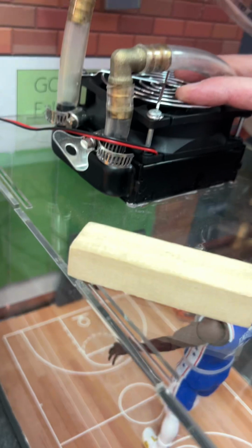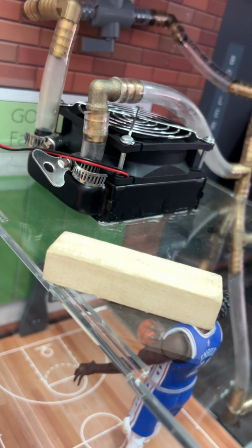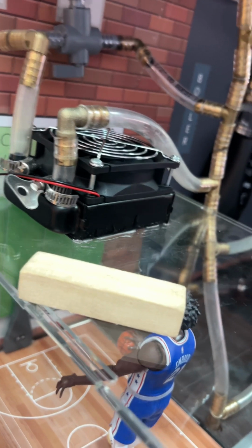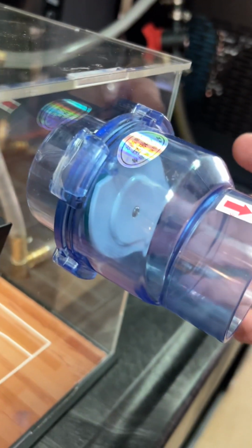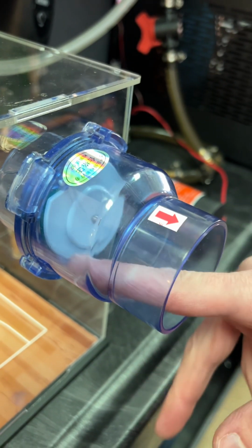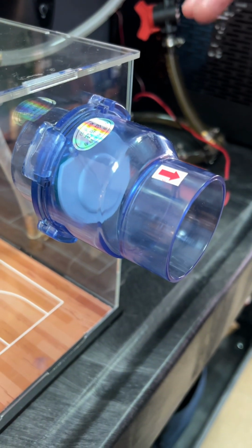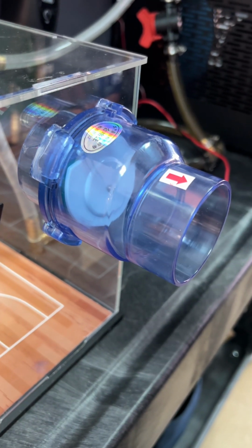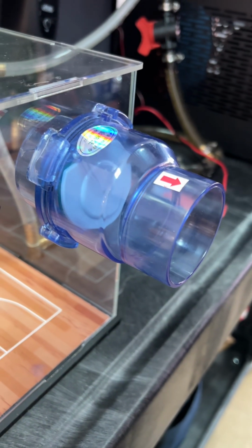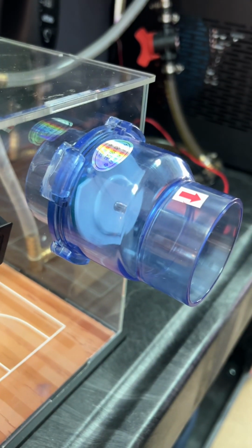A few other things. I talked about the fan blowing into these units. Just like a classroom, if we blow air in, the air has to go somewhere. In this case, these little dampers actually mimic what we call a barometric damper. In other words, if there's a certain amount of pressure in the room, the damper will open. So the more air blows in, the more the damper opens. It's simply a little flapper with a weight on it in this example.